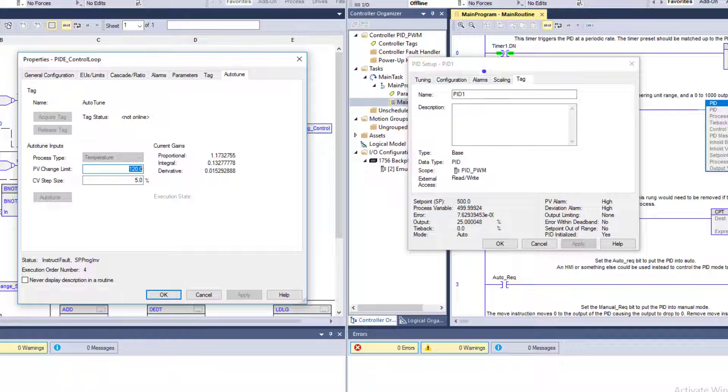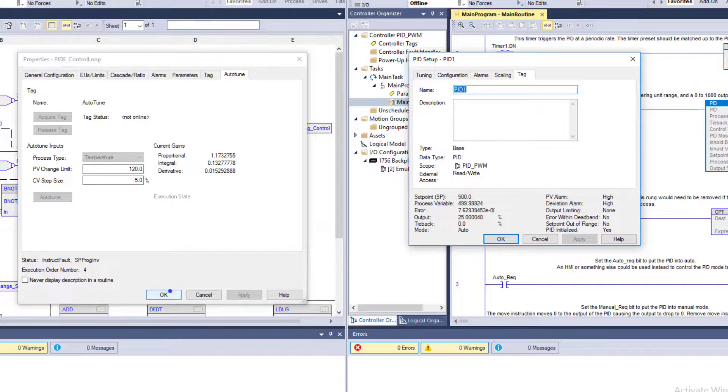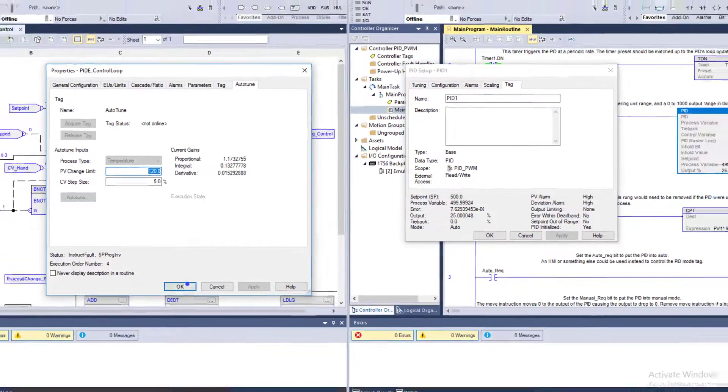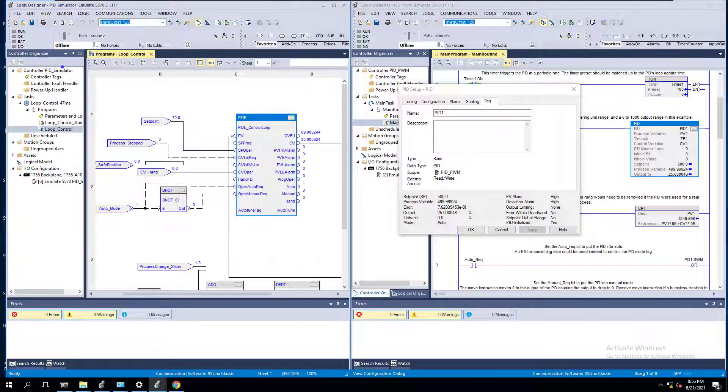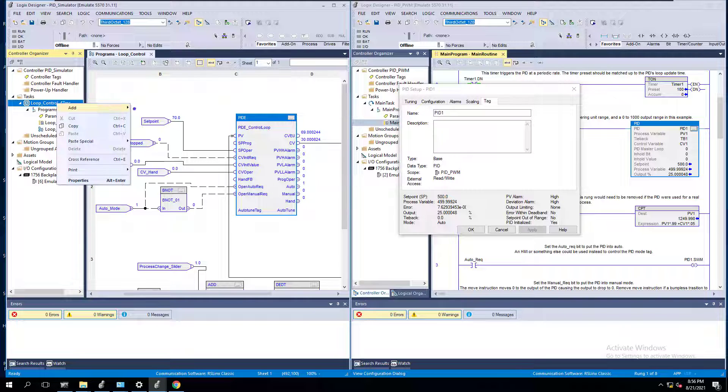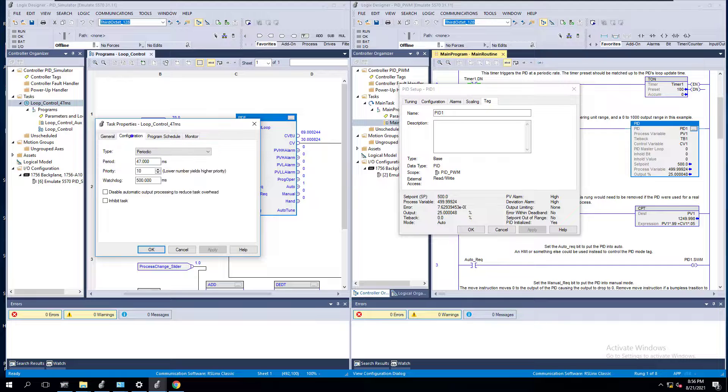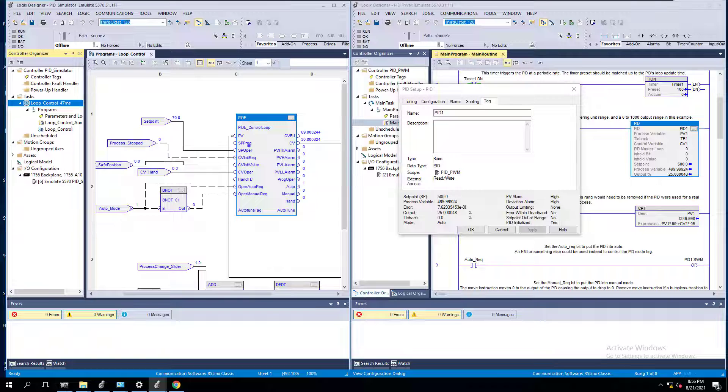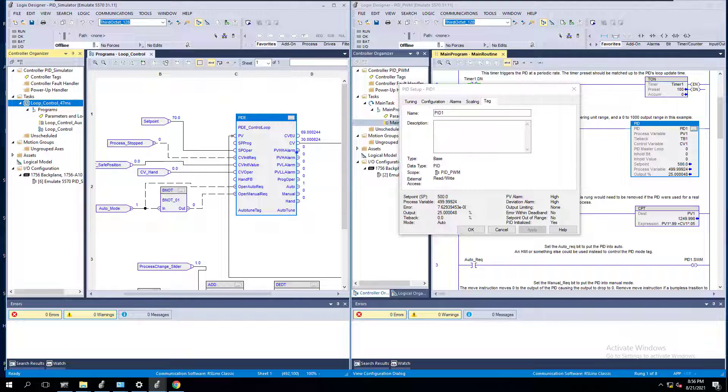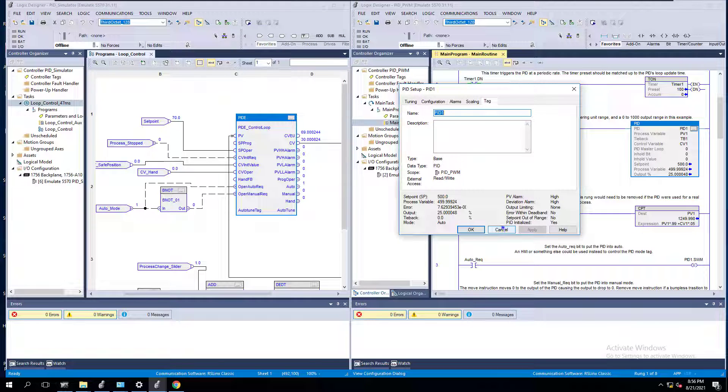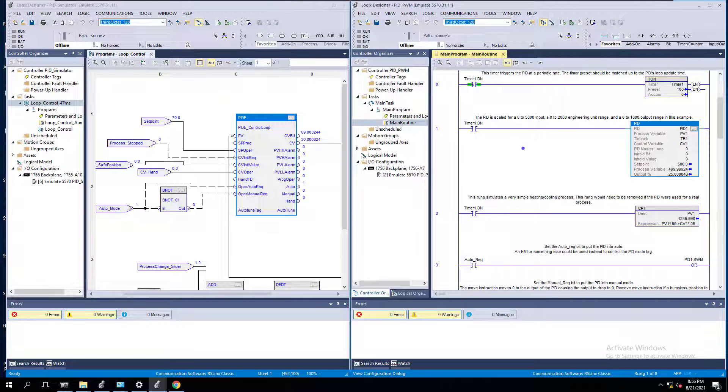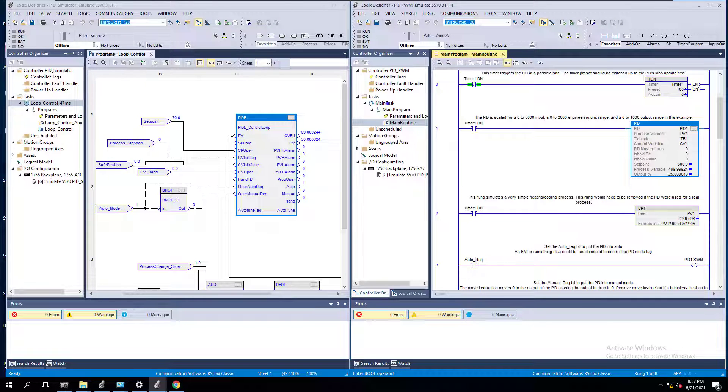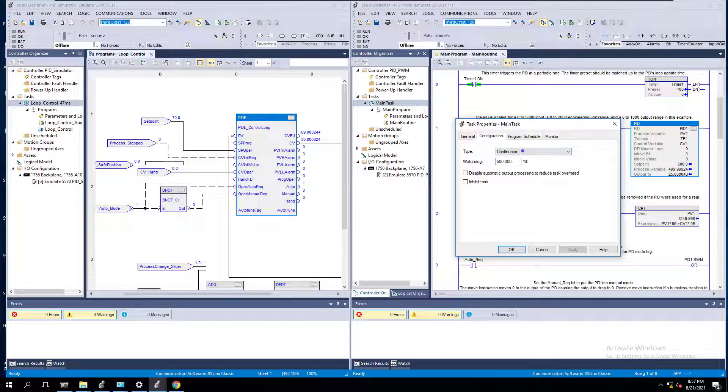When you look at the PIDE, I highly recommend that being inside of an actual periodic task. I have this PIDE inside of a periodic task. It's a periodic task of 47 milliseconds, and that's going to help me with my update rate based upon the time, the error of time, and everything like that. I wanted to give you a quick video to show you the two instances side by side. What are the true major impacts? What are the true major components of a PIDE and a PID?